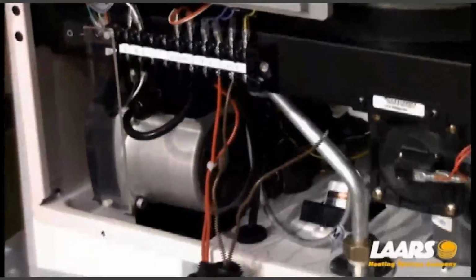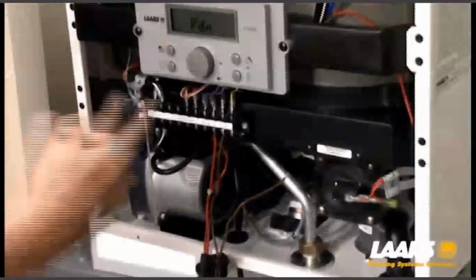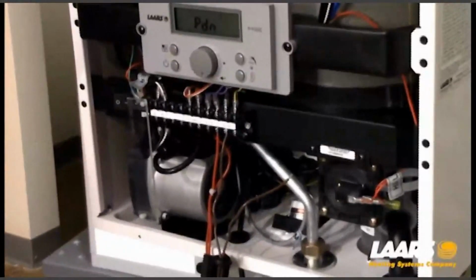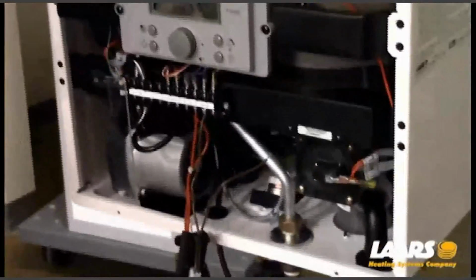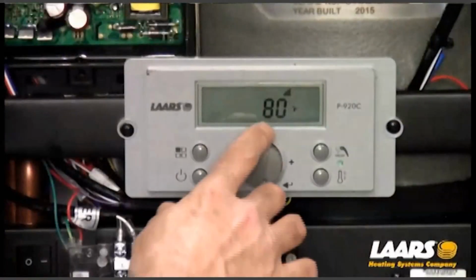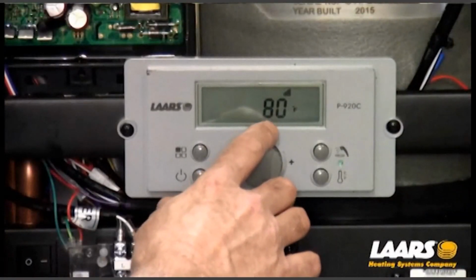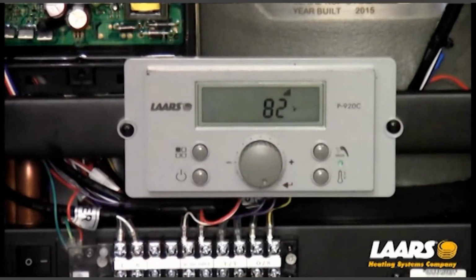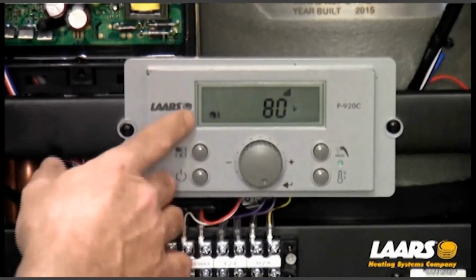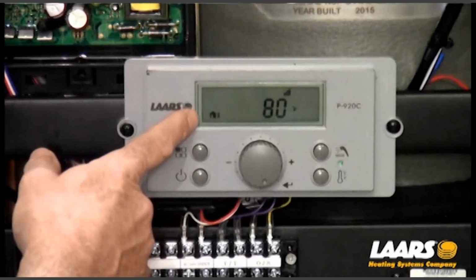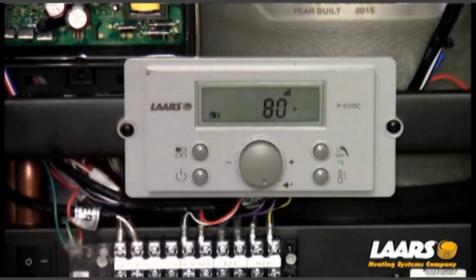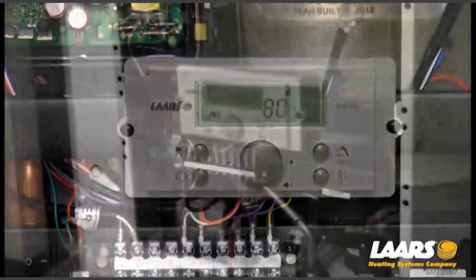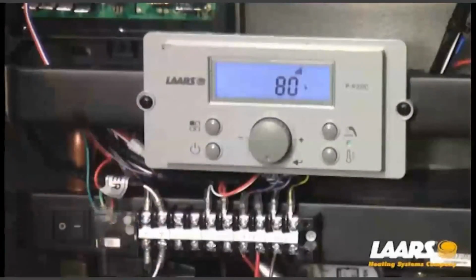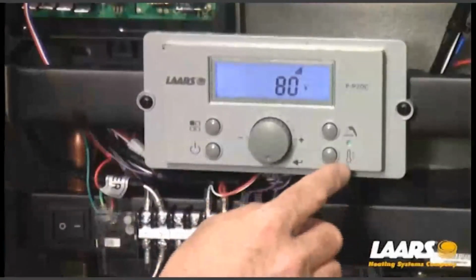Now with the sensor removed, I can repower up the display. It's going to go through its synchronization process, and we'll wait till it gets to the home screen. Now from the home screen, you'll see our setting right now. This is our water temperature in the boiler, reading roughly 80 to 82 degrees. We have our outdoor symbol for our outdoor sensor blinking. That's telling us we do not have an outdoor sensor installed. Now we can get in to set up central heat.